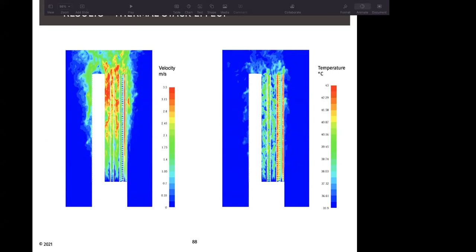So even if there is no wind blowing, this is for a no wind condition, you would get an updraft of air just because the hot air will rise from floor 0 to floor 57, and it will increase the velocity. So by the time we reach the top of the building, the velocity is 3.5 meters per second. This is purely due to the thermal buoyancy, the thermal stacking being created by the ODUs.